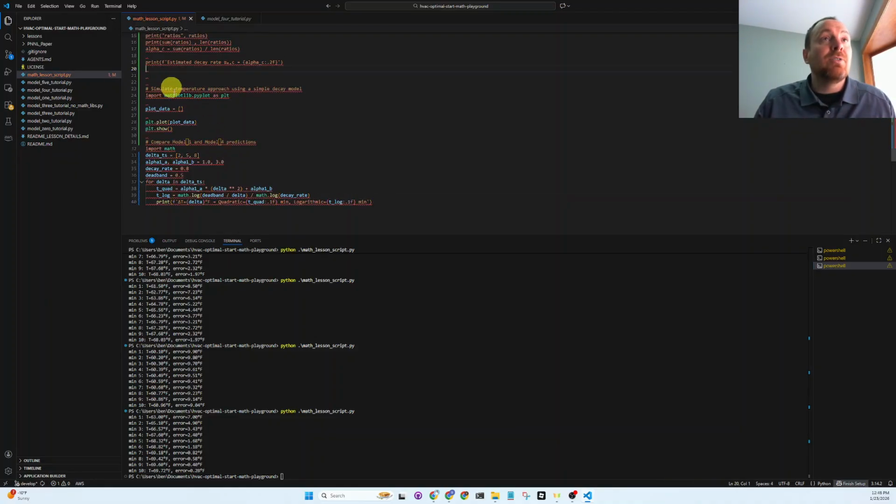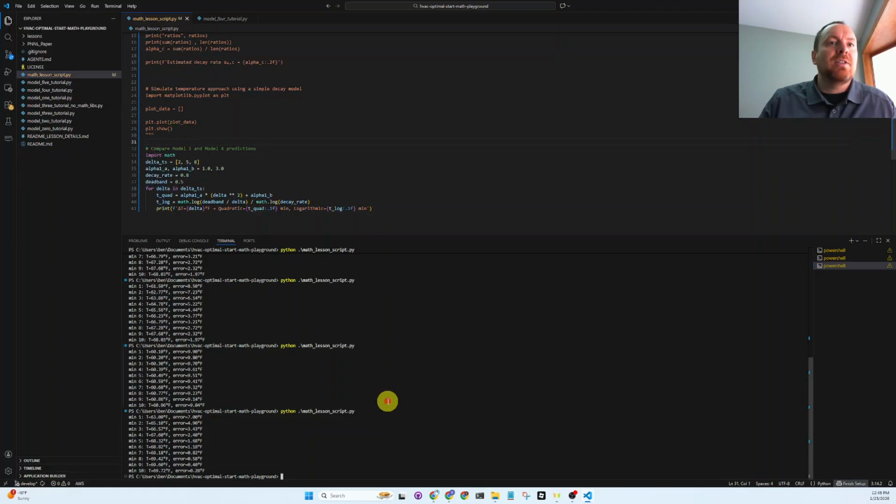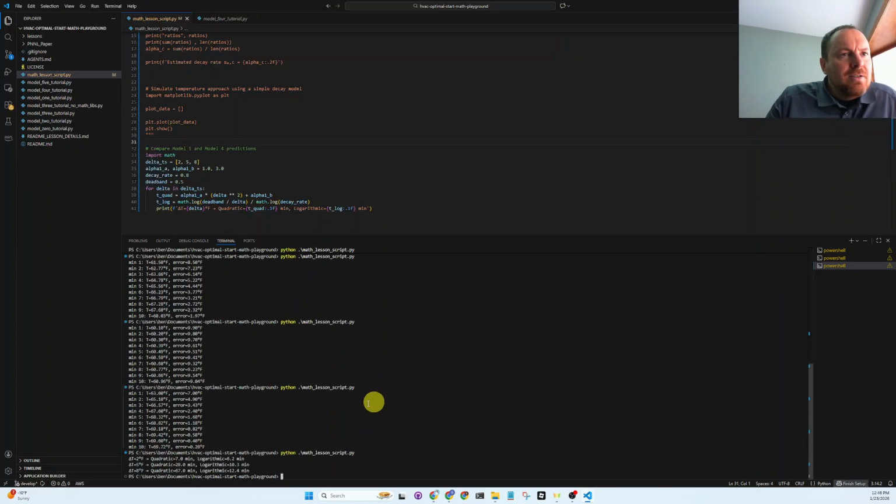Okay, so here are our delta temperatures right here: 2 degrees, 5 degrees, 8 degrees. That's the difference, it could be heating or cooling, doesn't matter. So it's the temperature above or below the zone set point when the HVAC system is off. And there's a delta that happens because we're not conditioning the zone anymore.